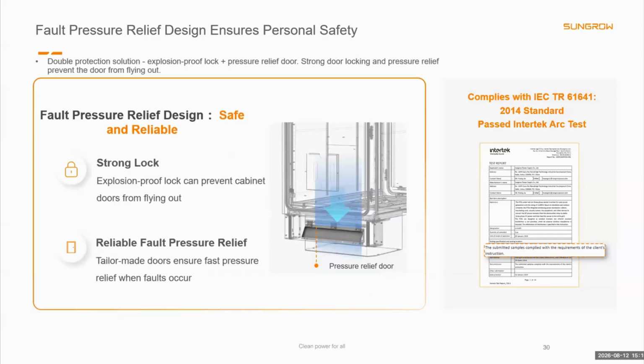The cabinet includes a dedicated internal fault pressure relief design. An explosion-proof lock helps to prevent the door from being thrown open, while a pressure relief door provides a controlled release path. The design complies with international standards and has passed Intertek arc testing.